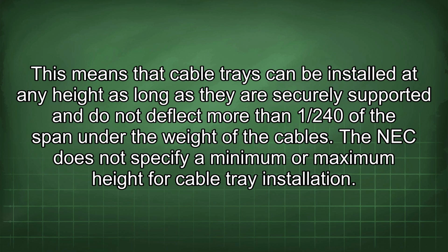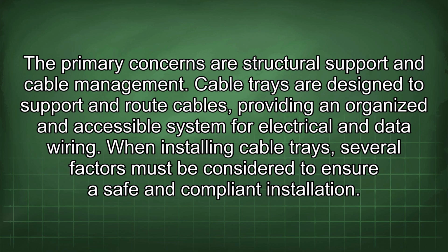The NEC does not specify a minimum or maximum height for cable tray installation. The primary concerns are structural support and cable management. Cable trays are designed to support and route cables, providing an organized and accessible system for electrical and data wiring. When installing cable trays, several factors must be considered to ensure a safe and compliant installation.